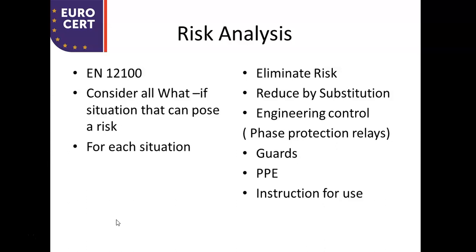In the next step, once you have your machine designed, you have to do a risk analysis. There is considerable guidance given in EN 12100 for conducting risk analysis for machinery. In a risk analysis you have to consider what-if situations that can pose a risk for the user, and for each such situation you have to take actions to eliminate the risk, or to reduce it by substitution, or to introduce an engineering control.